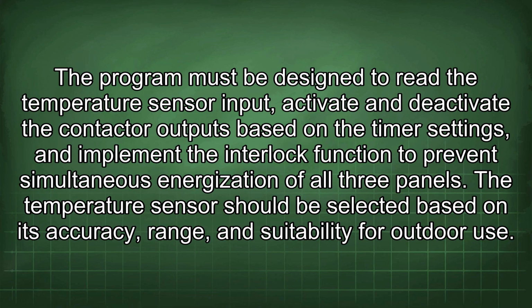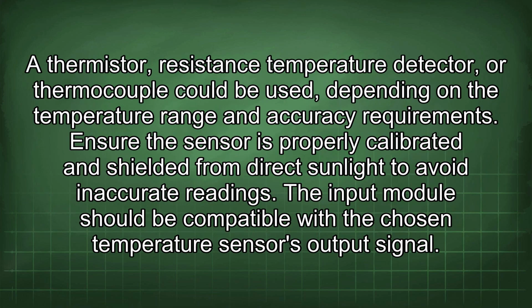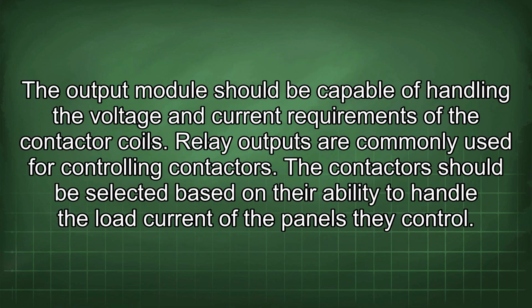The temperature sensor should be selected based on its accuracy, range, and suitability for outdoor use. A thermistor, a resistance temperature detector, or thermocouple could be used depending on the temperature range and accuracy requirements. Ensure the sensor is properly calibrated and shielded from direct sunlight to avoid inaccurate readings. The input module should be compatible with the chosen temperature sensor's output signal. The output module should be capable of handling the voltage and current requirements of the contactor coils. Relay outputs are commonly used for controlling contactors.